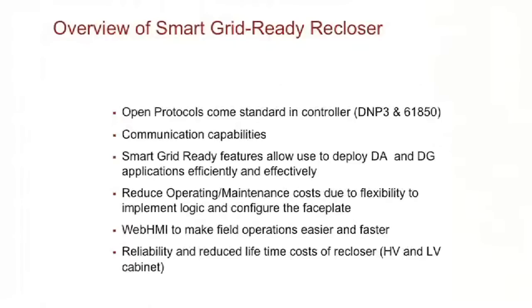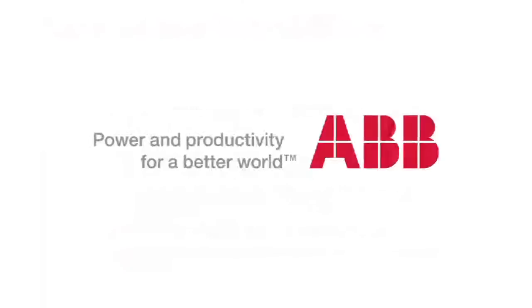And the last two, basically things that make it easy for you now, regardless of the technology. The web HMI interface. You can have a software, but if it makes it easy for the operators to connect a lot quicker, it helps you solve a lot of the issues you might have in troubleshooting or just performing your operations. And on the recloser as a whole, having a recloser that obviously is reliable. You're still going to need an apparatus that interrupts the current regardless of the technology. So having a product that has been proven in the market that reduces your maintenance requirements, it's key.